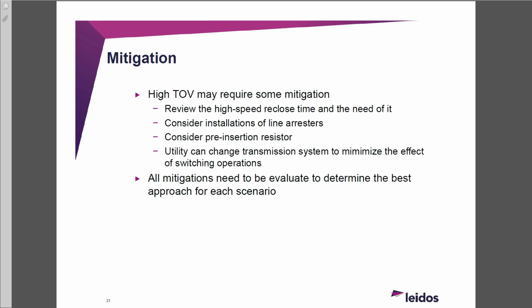Another thing is the high-speed reclose is there for stability, like someone was talking about today. So if you're going to change that, you've got to make sure that you perform stability studies, dynamic studies, to make sure that you're okay with changing that. The high-speed reclose is there for a reason. So changing it, you might open a can of worms. You're going to involve more work for yourself because you're going to have to do other things that were there for a good reason. So that's technically not our best mitigation, unless you're very close to the limit and changing it a little bit would fix it, but I would not recommend it.